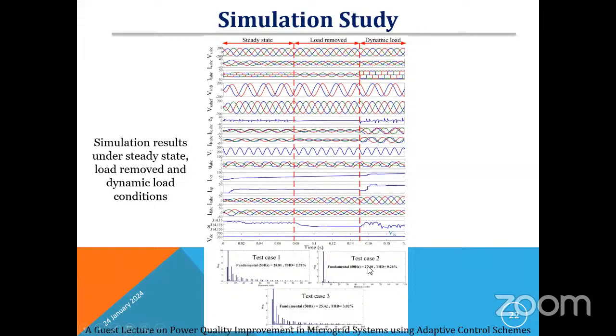In test case 2, the load remove condition, we have removed one phase of the load because we have to check the controller dynamic performance. We have manually removed one phase from the three phase load. At that time, we got very good THD performance, particularly in this load removed condition. From 28% we got 0.26%. So in the particular load remove condition, we got very good THD content.